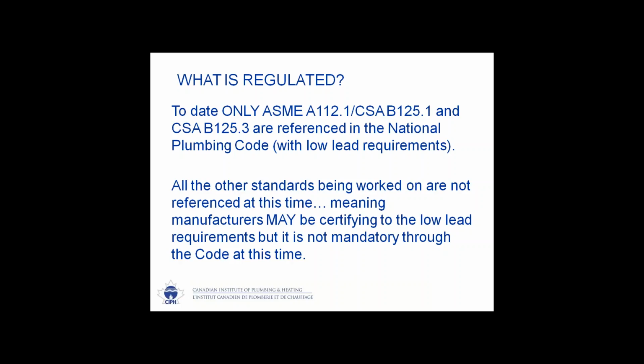So we've seen from the presentation that there are many standards that are in flux right now and changing and being updated. However, we want to come right down to it. What we're looking at is only B125.1 and B125.3, with their low lead requirements, that are now referenced in the code. And so it's only the products affected by the scopes of those two standards that actually have to meet the requirements of low lead today. So that is the state of things right now.